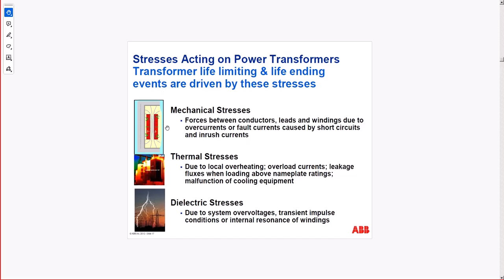And don't forget, these windings are in the coil of the transformer, mechanically positioned and maintained in position by different methods, and those may break down, and then you have loose windings collapsing and so on. Thermal stress. Thermal is overheating, right? So we have temperature monitoring on the transformers. We can also observe the temperature with infrared cameras. What the temperature does is accelerate the aging of the transformer. We don't want to leave that transformer on overheat. So how do we make sure that doesn't happen? It's easy. Don't overload the transformer. Make sure that you have pure oil and no sludge in the tubes that can clog the radiator.